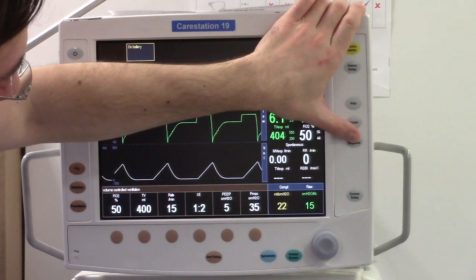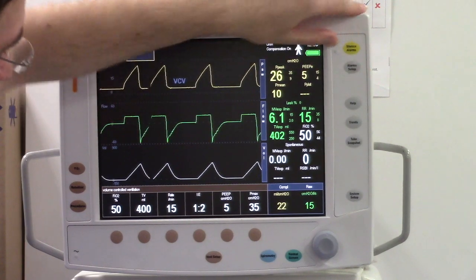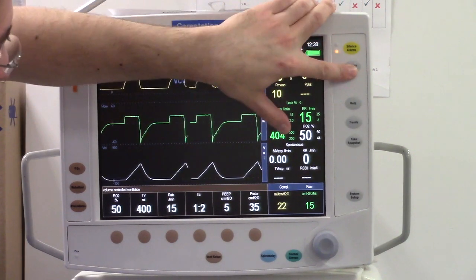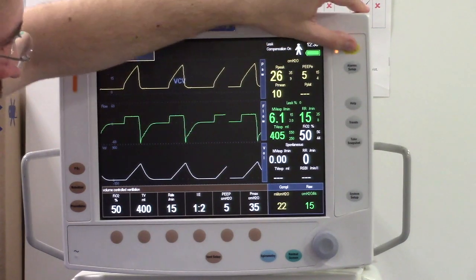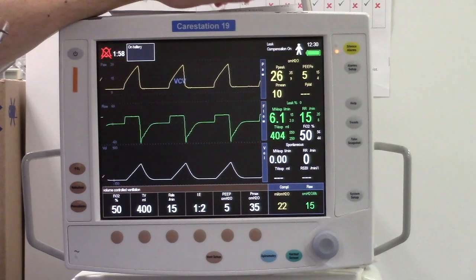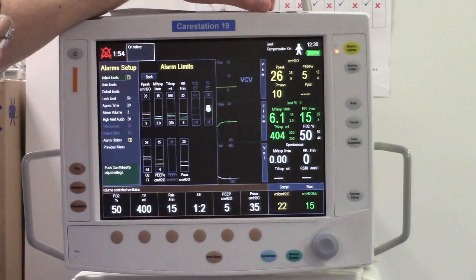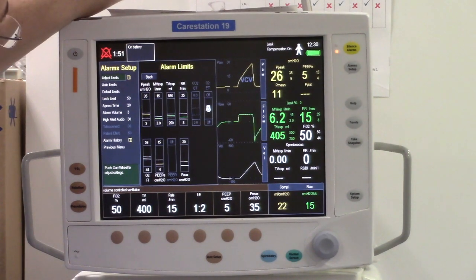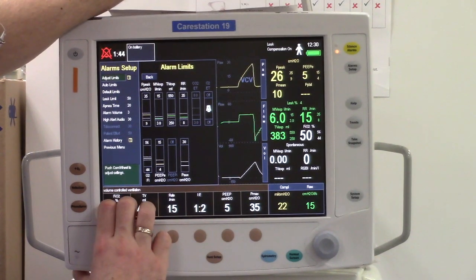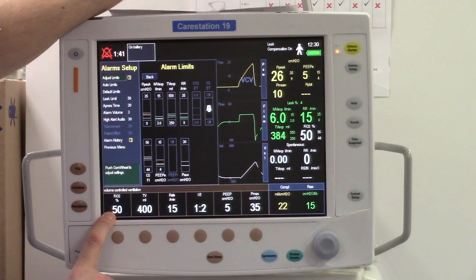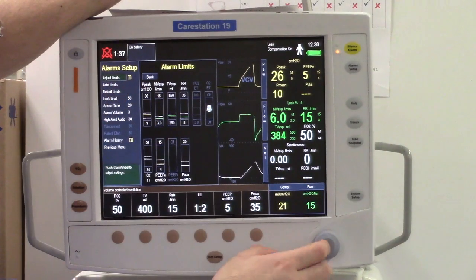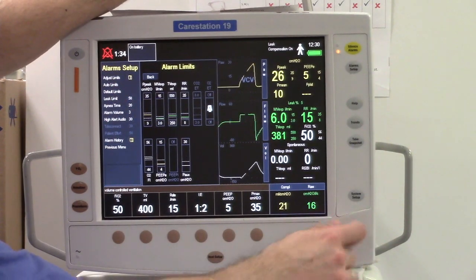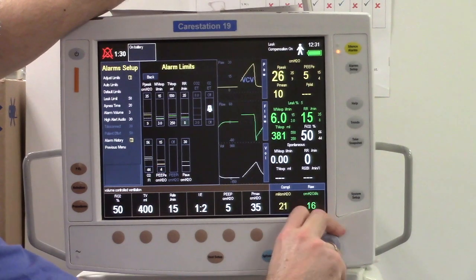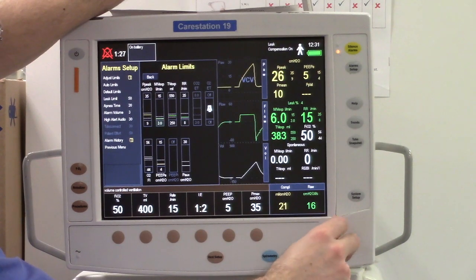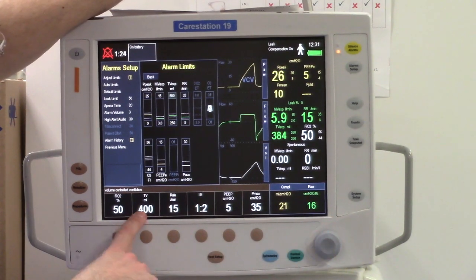This side has probably the most important buttons you'll be using here: silence alarm and alarm setup. Obviously, silence alarm does exactly what it says. It will silence an alarm. Alarm setup, over here, you don't just adjust your alarm limits, you can have a look at the history of the alarms. So, adjusting the alarm limits: press this button, you get this submenu, and the first option you have is adjust limits. If you press that, then you can navigate through the specific parameter which you want to adjust the limits for. For example, in our case, we know that we set the tidal volume at 400.